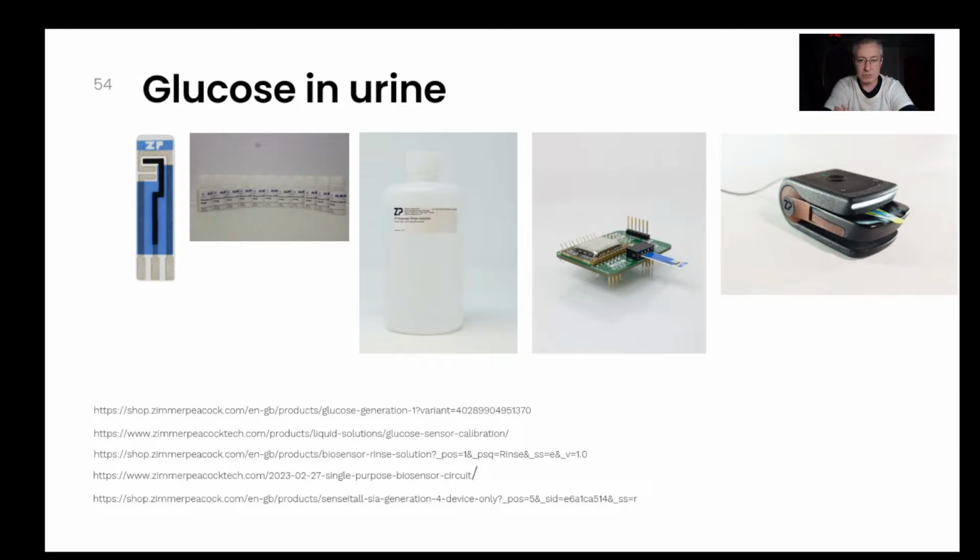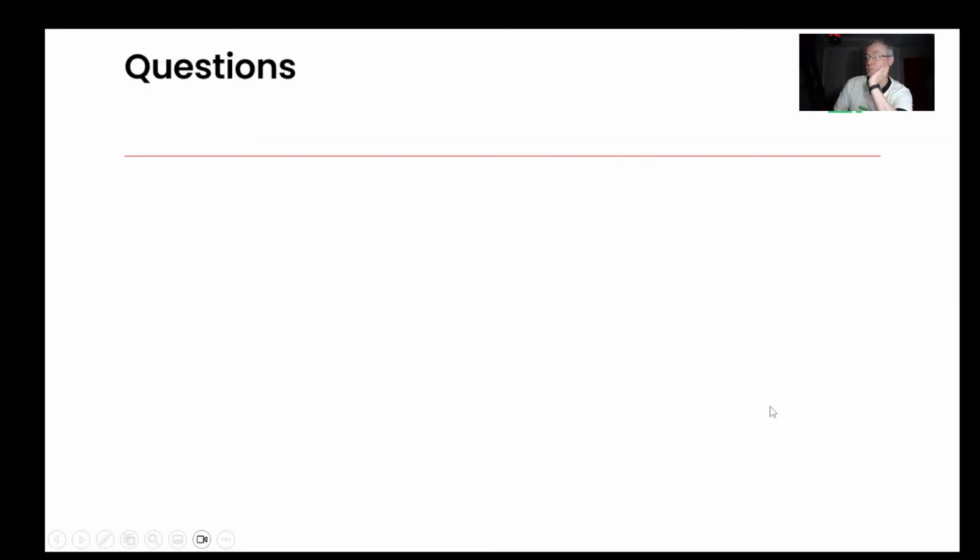No, if the pH is 4.8 or the pH is 8, that itself is a source of variability and a difference. And you get a difference. The glucose is otherwise the same. The sensor will respond differently because of those different pHs. Question number 1. All right.